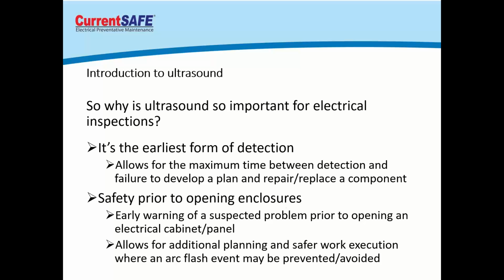Why is ultrasound, or an ultrasonic tool, so important to us? It is the earliest form of detection for an anomaly, so we have the greatest amount of time from early detection to extend the life of our customers' electrical distribution equipment, regardless of what it is. The earlier we can detect it, the better off we are for making adjustments, cleaning things, or making a repair if we have a bad component or termination we're listening to. It is our earliest way to extend the healthy life and condition of the electrical distribution system.